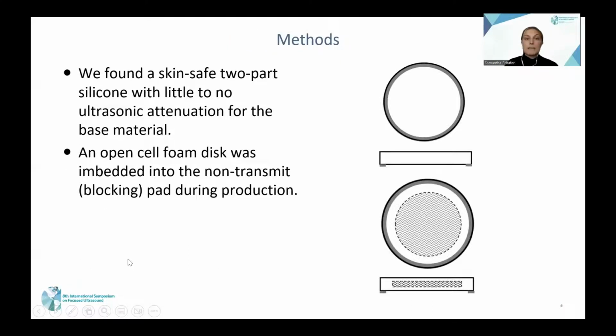So we found a skin-safe 2-part silicone with little to no acoustic attenuation for the base material. On the right-hand side of the screen on the top is a schematic for the transmitting pad. As you can see, it's just plain material. So that is the transmitting version. And then we had an open cell foam that was cut into the shape of a disc that was embedded into the non-transmit pad, which is down here on the bottom. And again, that foam is going to block the transmission of ultrasound, and that was embedded into the base material during production.